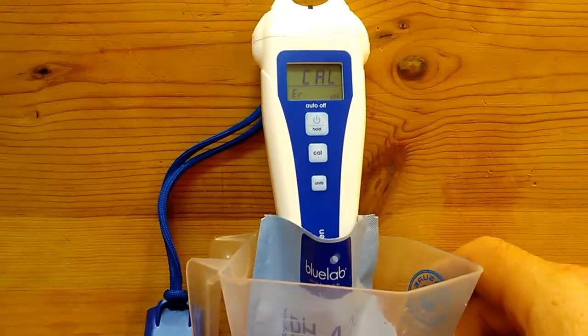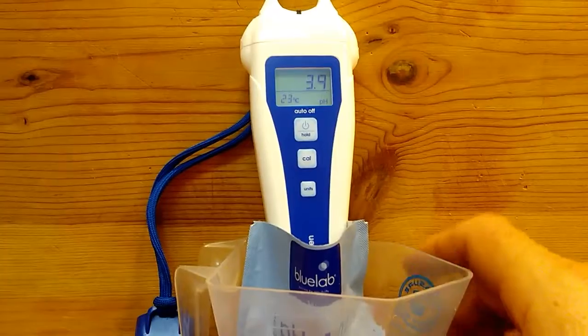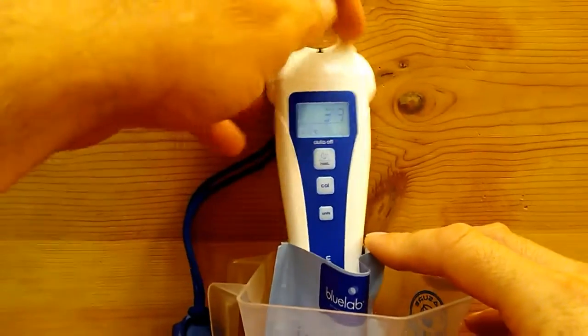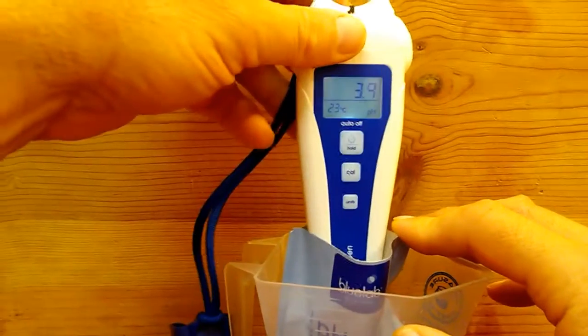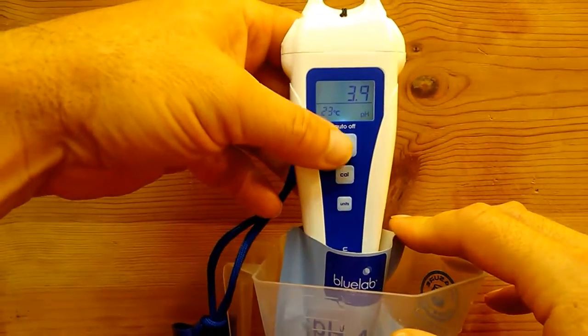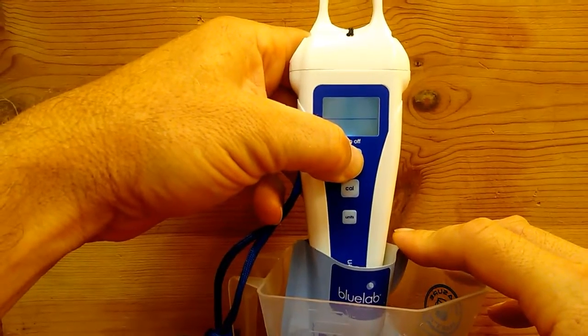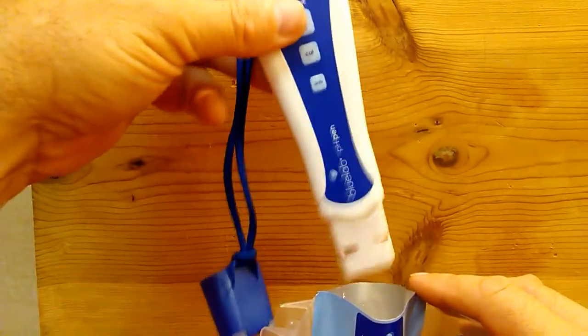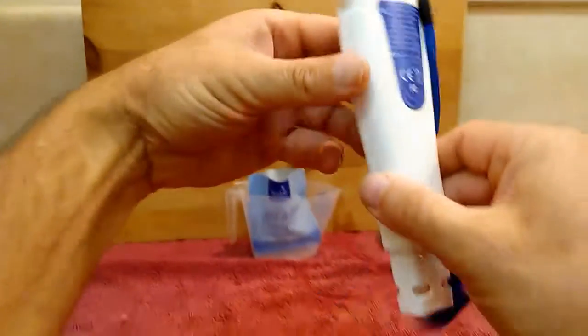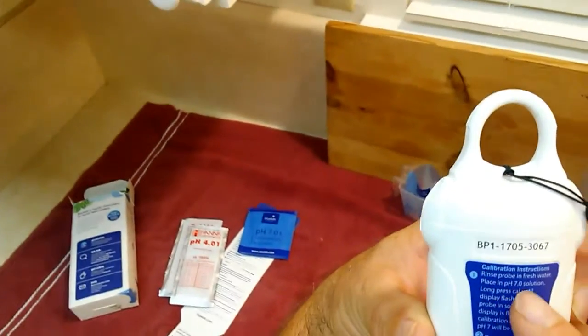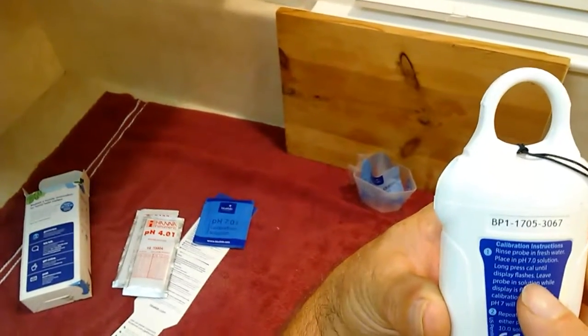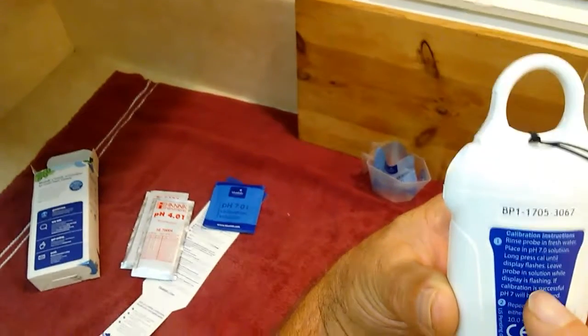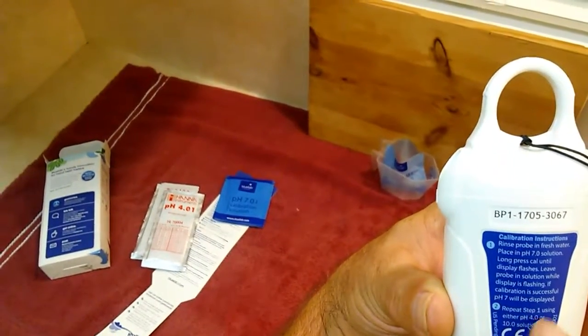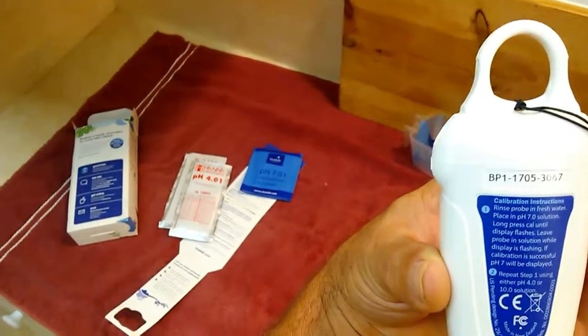Yeah, ER. Maybe that means, hey buddy, you're calibrated as calibrated can get. Although that would stipulate error to me, although I can't find anything anywhere that stipulates anything. Maybe it's on the calibrating instructions. Place in 7.0 solution. Long press cal. Leave probe in solution while display flashes. If the calibration is successful, 7.0 will be displayed. Repeat step 1 using either 4.0 or 10.0 solution.